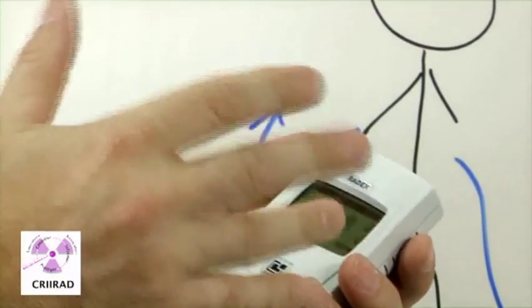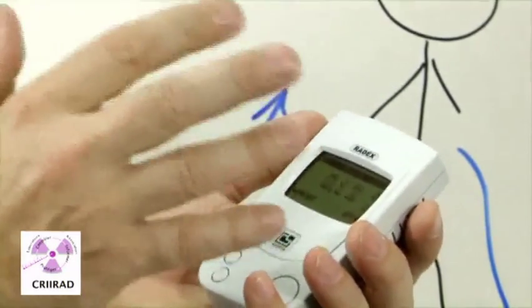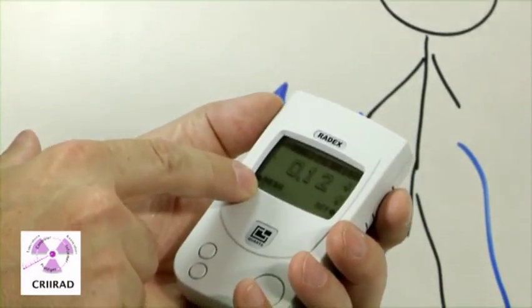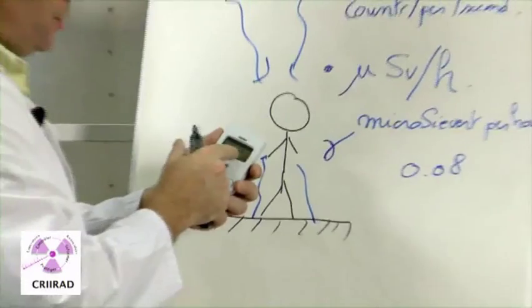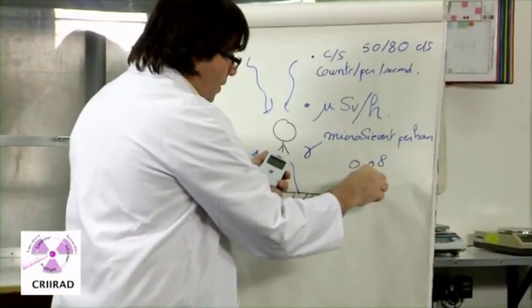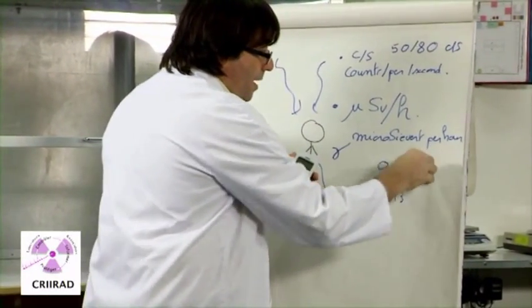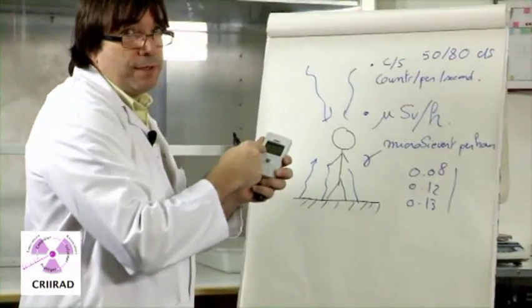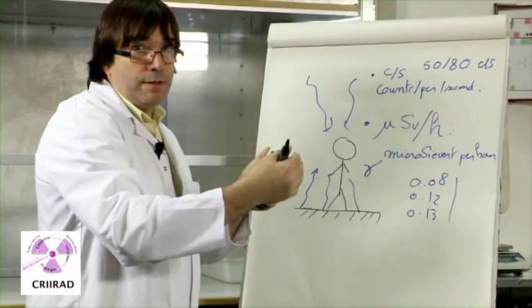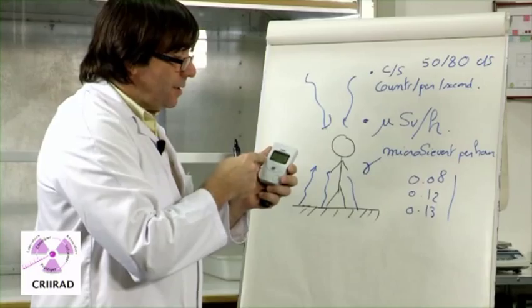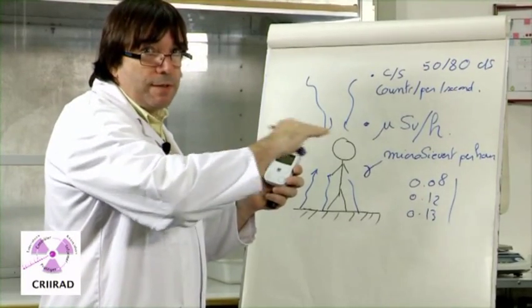So, the measurement will take, let's say, 2 to 4 minutes. At this moment, we have 0.08 microsieverts per hour. Now, 0.12, 0.13, and I am waiting for it to finish its counting cycle, so that it will give us a correct value.